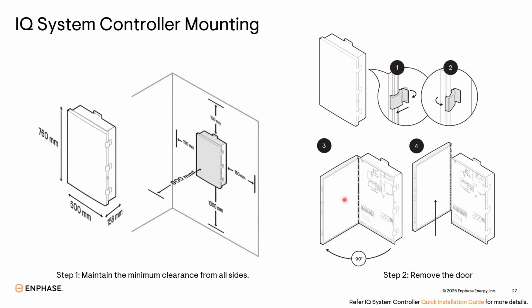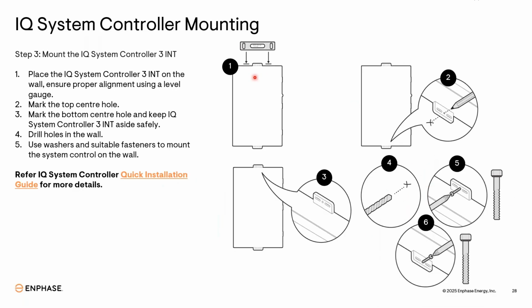Now coming to the mounting parts. Your system controller will be wall mounted. You need to leave a minimum spacing of 150 mm on all three sides, and from the bottom you need to maintain a distance of 1000 mm, and from the front you need to maintain a distance of 900 mm for the door opening. You open the latches, rotate your door 90 degrees and lift it up, and your door will come out. Once the door is out, you put your controller over the wall, level it, mark the holes and drill, and with the fasteners you can mount your controller.